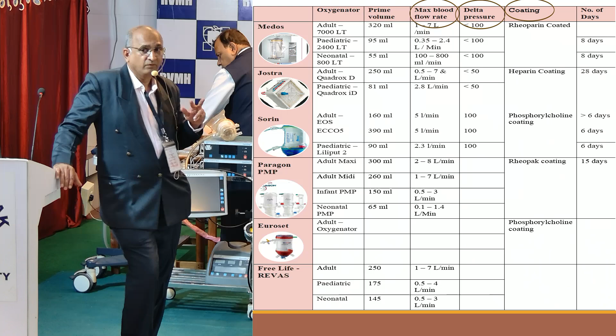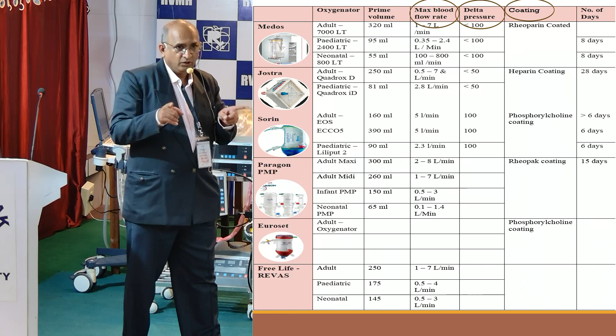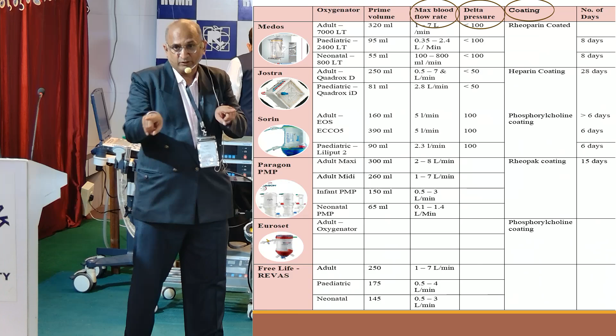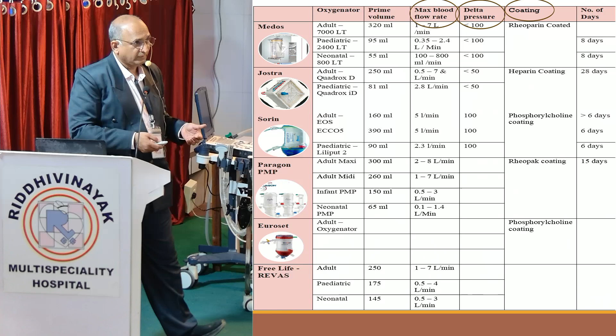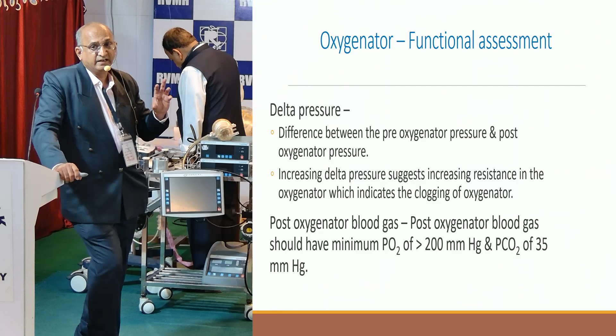So there will be 2 oxygenators. And how will you put these 2 oxygenators? In parallel to each other, not in series. In series, you won't have any benefit. It has to be parallel. So you have to put a Y connector. One will go to the first oxygenator, the second connector will go to the second oxygenator, and similarly a reverse Y. I'll come to that when I go to the circuit. Fine. Then how will you monitor the oxygenator function? By delta pressures or transmembrane pressures. So we measure P2 and P3.